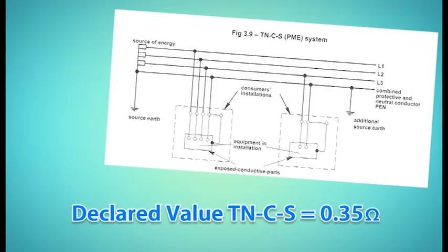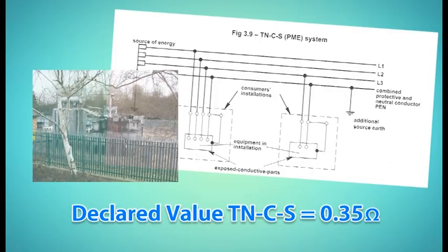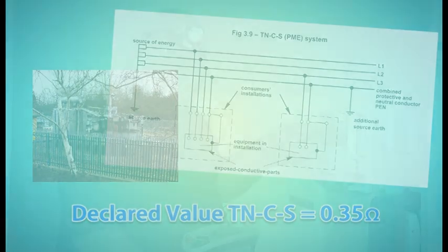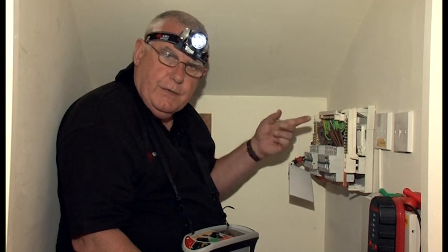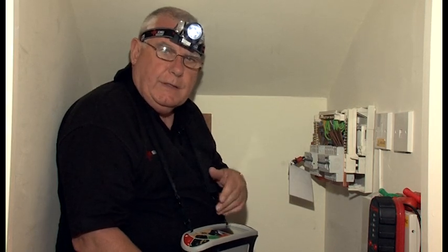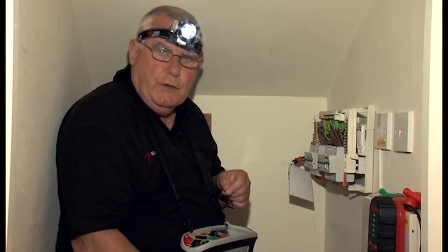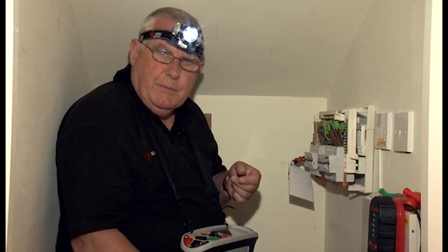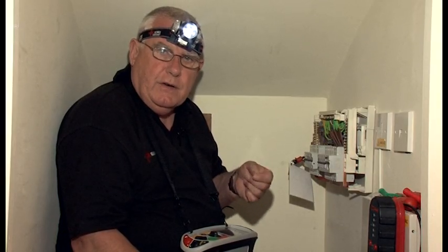So our 0.17 is lower than this, most likely accounted for due to being close to the local supply transformer. But don't forget that where network switching takes place, this can also cause impedance values to go up or down. Now I've reconnected the earthing conductor and will now undertake the reading of the respective short circuit current. This is taken between line and neutral on the incoming side of the main switch.